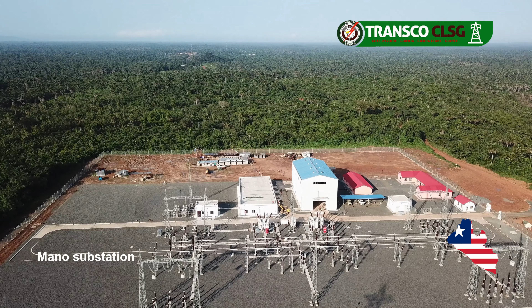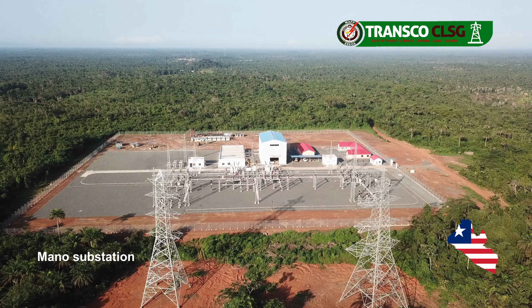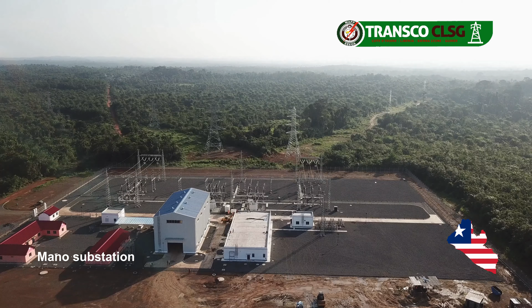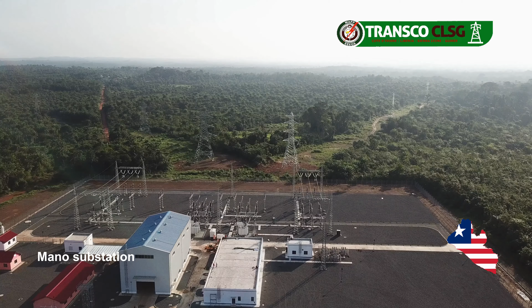This is an outside view of the next substation after Buchanan, which is the Mano substation. This indeed is the biggest substation of our network. It is connected to the Mano hydro power plant, which is an 88 megawatt power plant. In this substation, we have 2 big power transformers of 70 MVA. It is a 3-winding power transformer 225/132/66 kV, and also in this substation there is a 35 MVA SVC.